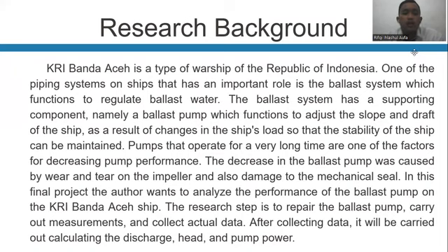can be maintained. Pumps that operate for a very long time are one of the factors for decreasing pump performance. The decrease in ballast pump performance was caused by wear and tear on the impeller and also damage to the mechanical seal. In this final project, the author wants to analyze the performance of the ballast pump on the KRI Banda Aceh ship. The research steps are to repair the ballast pump, carry out measurements, and collect actual data. After collecting data, I will calculate the discharge, head, and pump power.